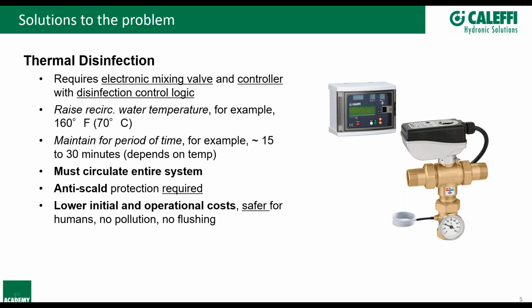Now in the European markets, usually they're jacking up that temperature to about 160 degrees, maintaining that distribution temperature out through the system for typically 15 to 30 minutes. It really depends on the size of the building and how long it takes to get back.